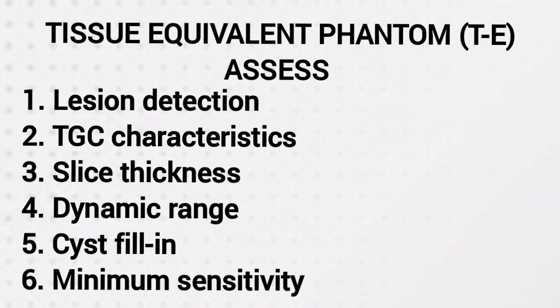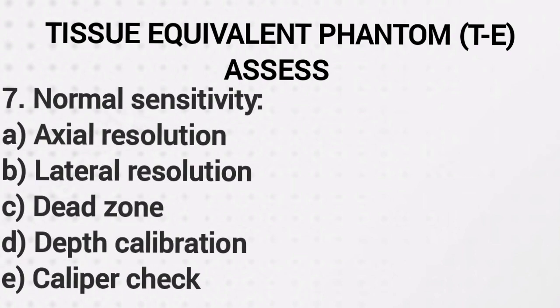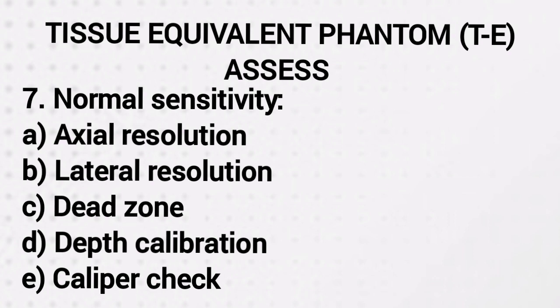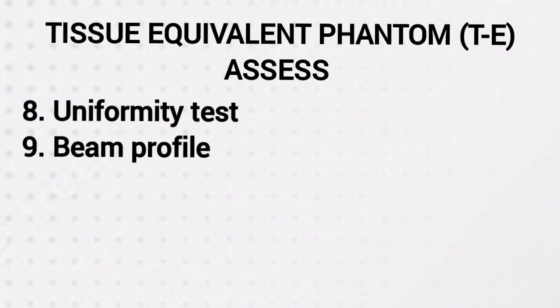Tissue equivalent phantom, TE phantoms. These are the most commonly used testing devices today. It provides much more realistic assessment of clinical performance than the AIUM test object. It gives accurate assessment of grayscale or tissue characteristics such as attenuation and scattering. In addition to all the parameters that can be checked with the AIUM test object, TE phantoms provide the assessment for lesion detection, TGC characteristics, slice thickness, dynamic range, cyst filling, sensitivity, normal sensitivity tests like the axial, lateral resolution, dead zone, range accuracy or depth calibration, caliper check, uniformity test, beam profile.